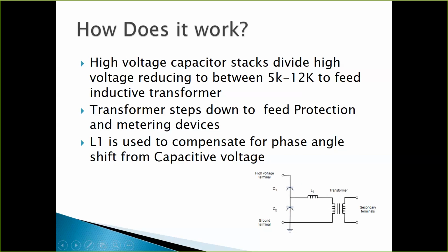If you have a delta line, a long delta line, you tend to have capacitance from your long line to earth. So you have some ferroresonance circuits in here that dampen those harmful signals that cause heating of your devices. And again, the L1 is used to compensate for your phase angle shift from a capacitive voltage. Very simple. This part right here is oil filled at the bottom of it, and your stack has oil in the top of it where the insulators are housed.